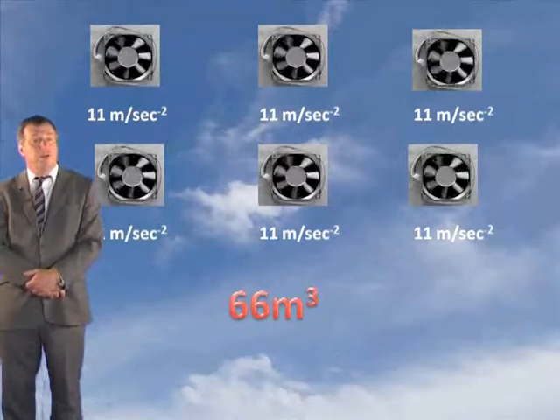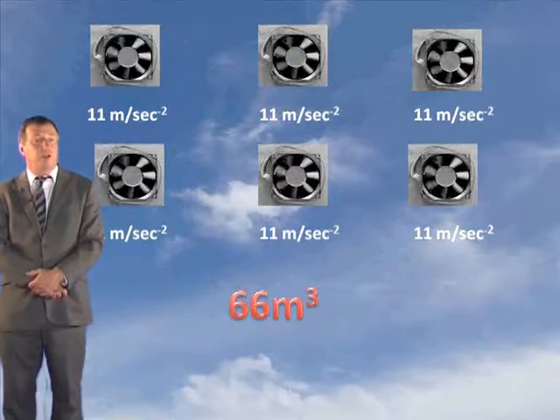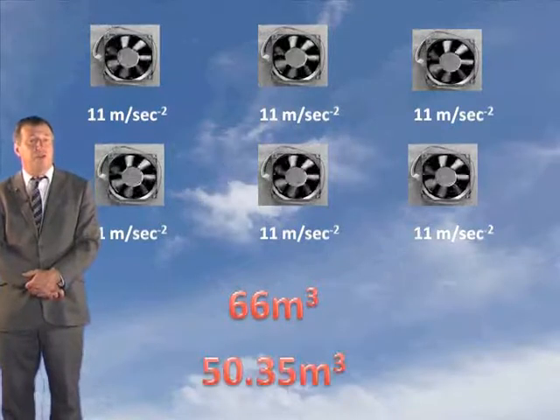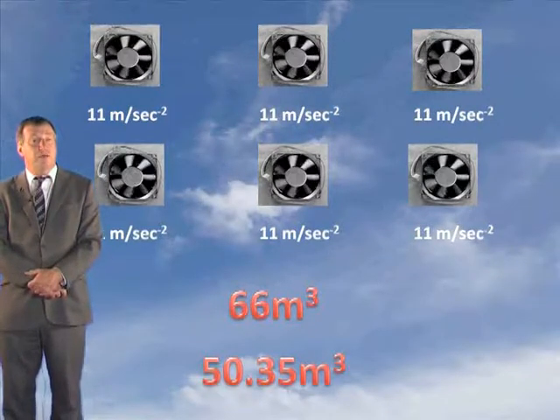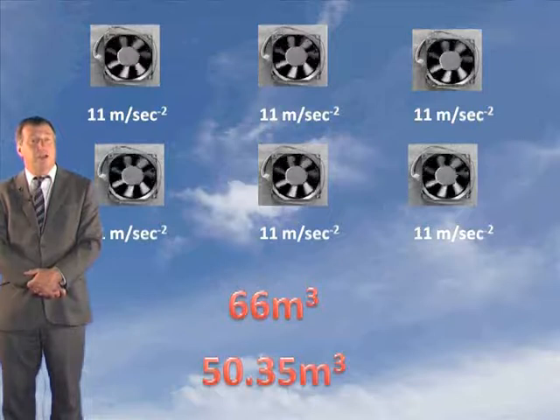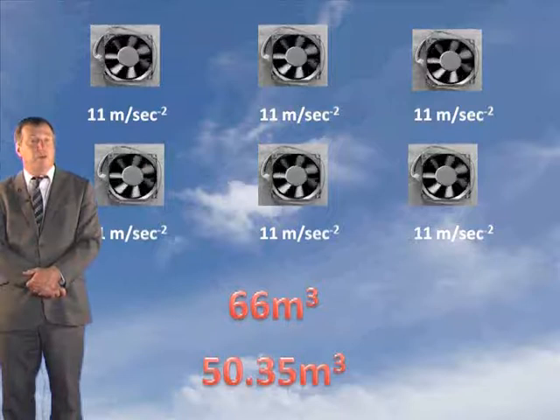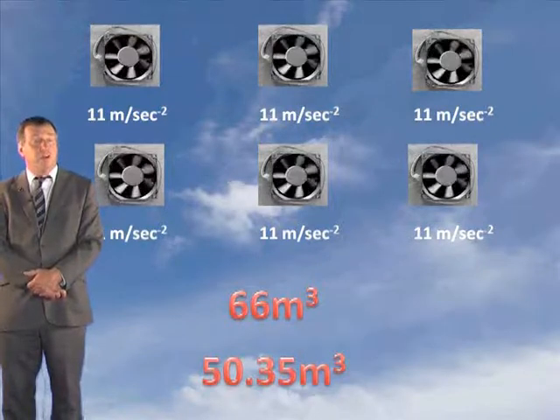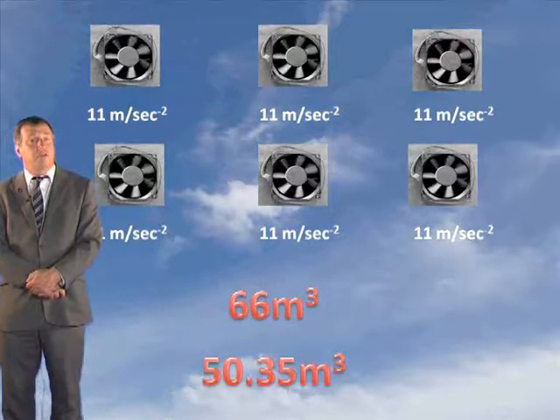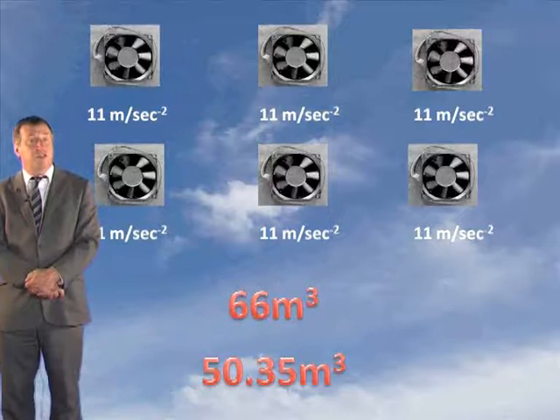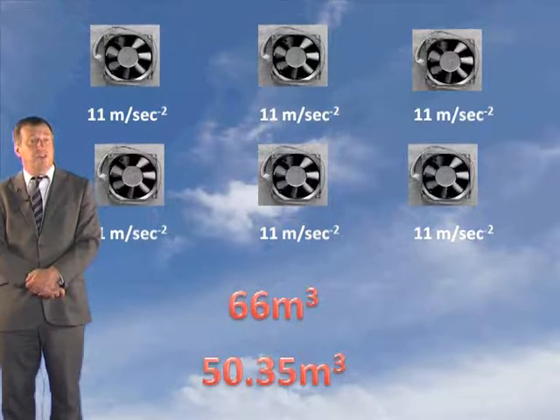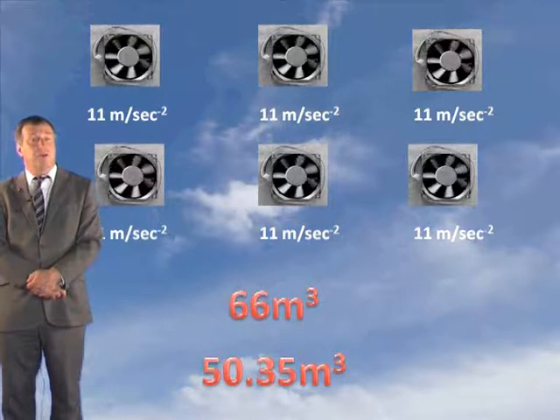The required volumetric extraction rate in that example was 50.35 cubic metres per second, but this figure has no significance here, and neither does the 55 cubic metres per second that would be extracted if one of the fans were lost to fire. We're interested in the maximum possible extraction rate that can take place in the building, and for our example this was 66 cubic metres per second.